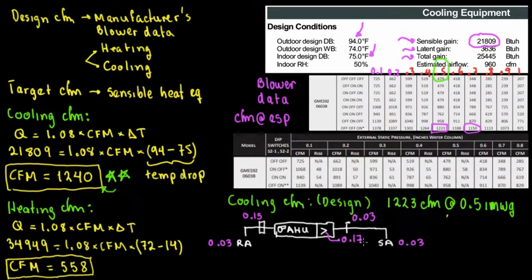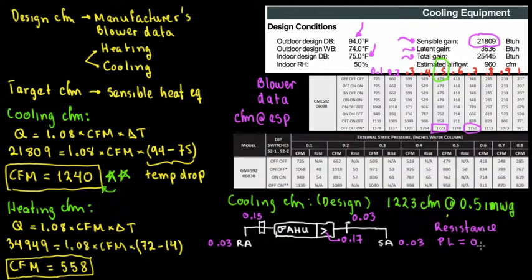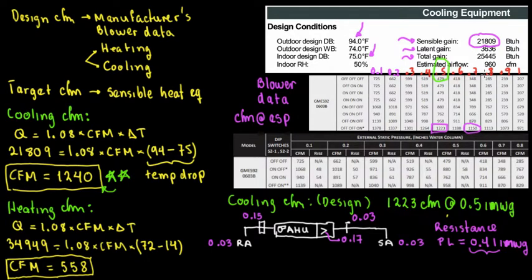Adding all these up, the total resistance or pressure loss equals approximately 0.41 inches of water column. Since we are at 0.41 and we selected the 0.5 speed point, we're able to achieve the proper CFM. We're in the safe zone.